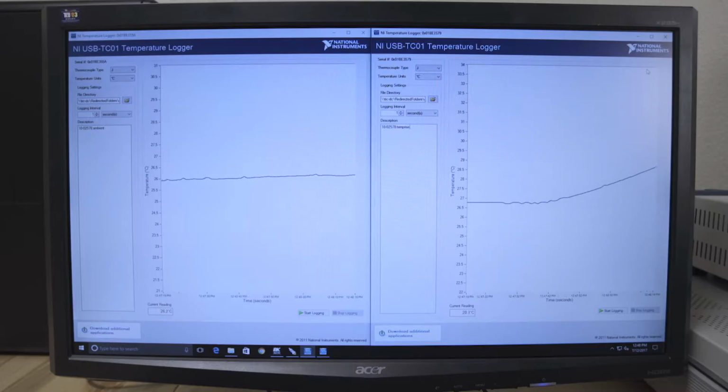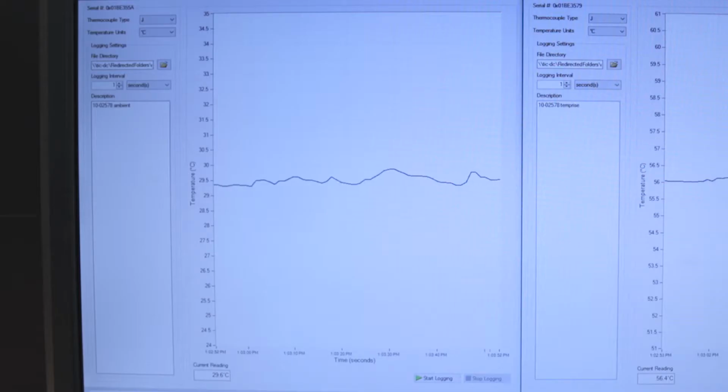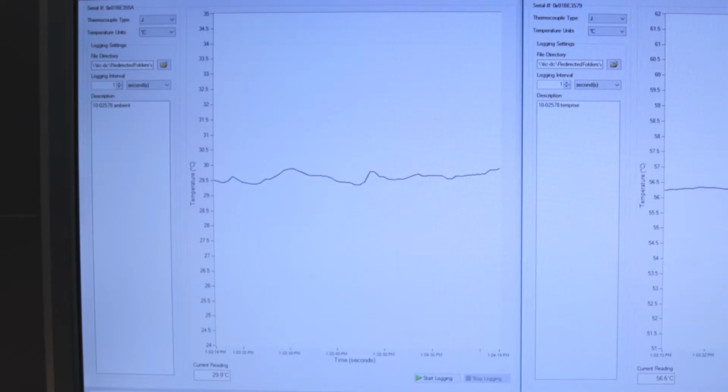The electronic load current is slowly increased until a 30-degree temperature rise is stabilized. Before the temperature can be considered stable, the connector must stay within 2 degrees Celsius for 3 consecutive 5-minute intervals.